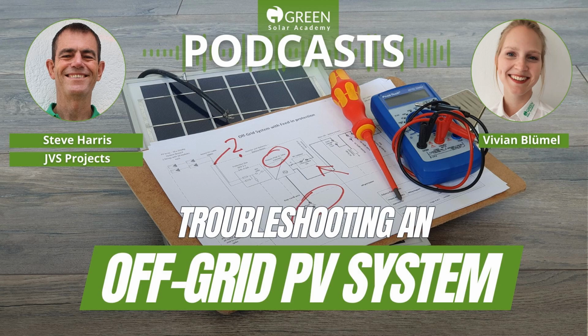Anywhere there's a dusty condition, which is pretty much all of Africa, those inverters, when working hard during the day, have fans sucking air through at a fairly significant rate. If you've choked the inverter, it's going to overheat components, which will slowly become more inefficient, and prior to failing, they may just become poor. They just don't want to work so well.